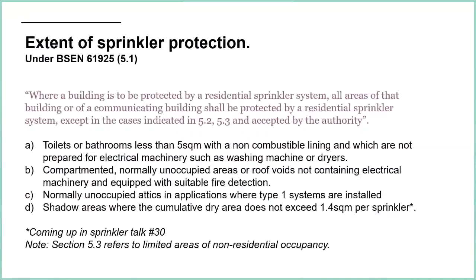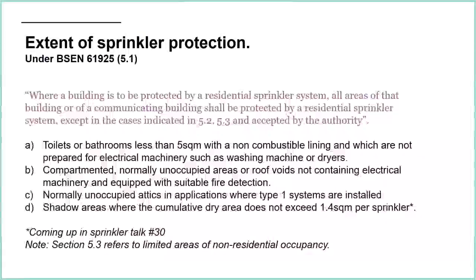A type one system is basically for domestic houses. So for residential blocks of flats, you wouldn't be allowed to omit sprinkler protection in unoccupied attics, whereas in a domestic house you would be. Then we have something called shadow areas, where the cumulative dry area does not exceed 1.4 square metres per sprinkler. I'm not going to go into that in this episode - that's coming up in Sprinkler Talk number 30, which covers residential sprinklers part three, where I'll explain shadow areas and how to calculate the cumulative dry area.